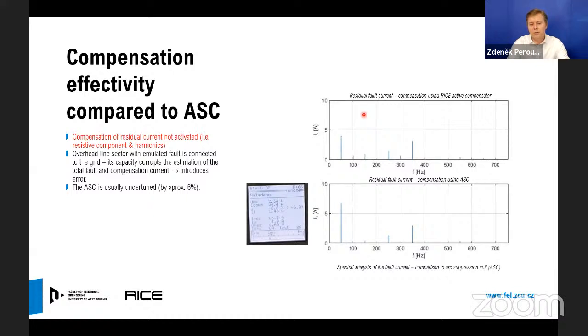And we also stressed our device with a specific emulation of the earth fault, when the earth fault was emulated on a part of the grid which was switched off. The earth fault was made, and then we switched this section of the line on. And of course, the fault current occurred immediately after switching on this section of the grid.